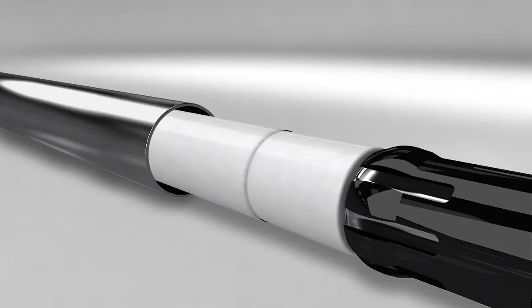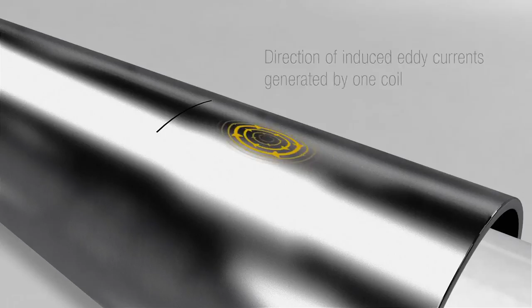Multiplexing is key here. The coils are driven sequentially in a clever pattern. This enables the Defy probe to examine the entire circumference of the tube with no mutual interference between the coils. The result? High-definition data. The Defy probe can therefore detect and size defects typically detected by bobbin probes, but also circumferential defects.